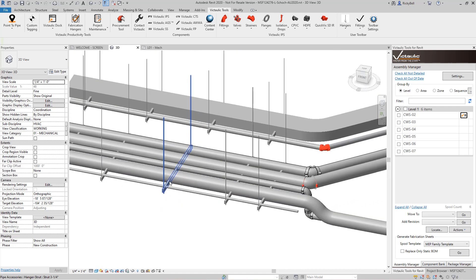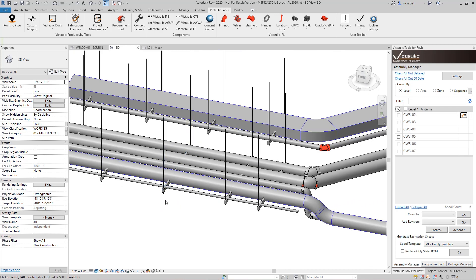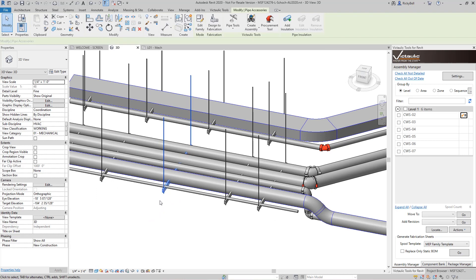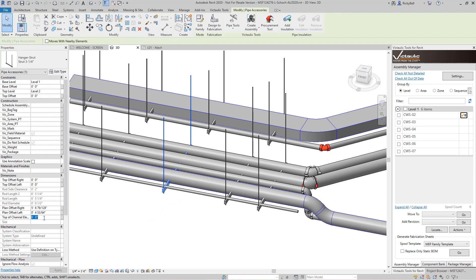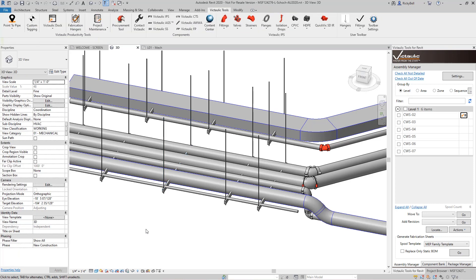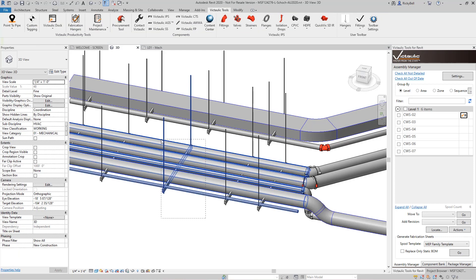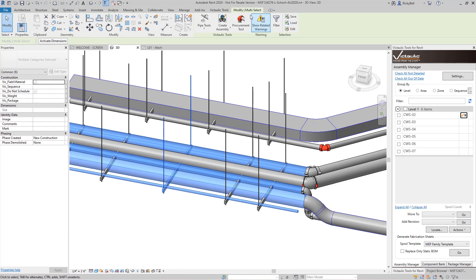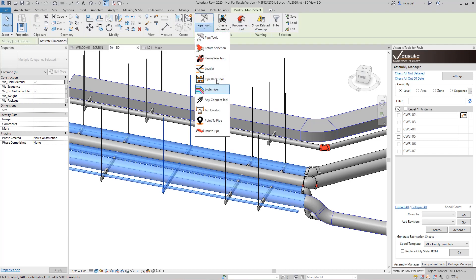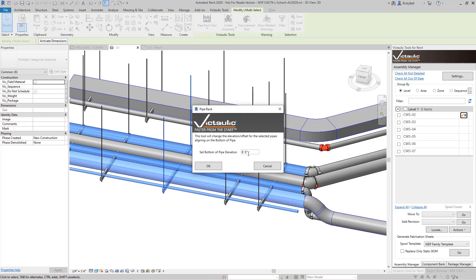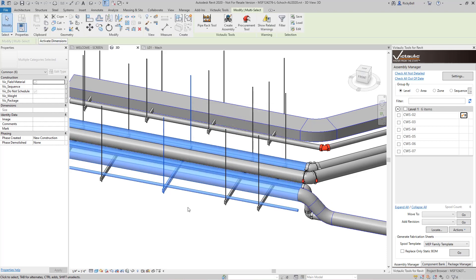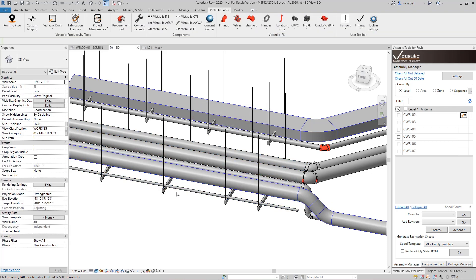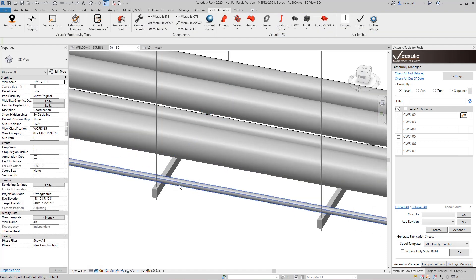So to fix this, let's take a look at where our hangers are. Our hangers have a center line elevation of 9 feet. So let's make everything in our selection match that. I'll do this rack first. Now I can highlight multiple things in my selection right here and run under the pipe tools, the pipe rack tool. It's going to, by default, show me the lowest point that it could find, which was eight foot six. But I want to drive this instead of read from it. So I'm going to say nine feet and click OK.